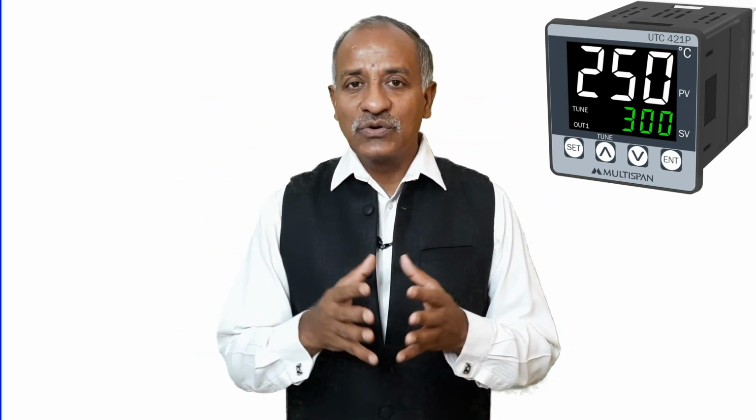But there are many things along with that. Say for example, at the moment I am in this particular room. Assume that we have a temperature gauge in the room and the temperature is 30 degrees, but there is an error of 30%. So instead of 30, it will be showing 39. But how does it matter? It hardly matters. But assume that the same temperature gauge is now put in a laboratory where we are doing testing. Any change in the temperature can result in a variation in the readings or in the entire process. So there, even 10% is a high variation with respect to the measurement system.